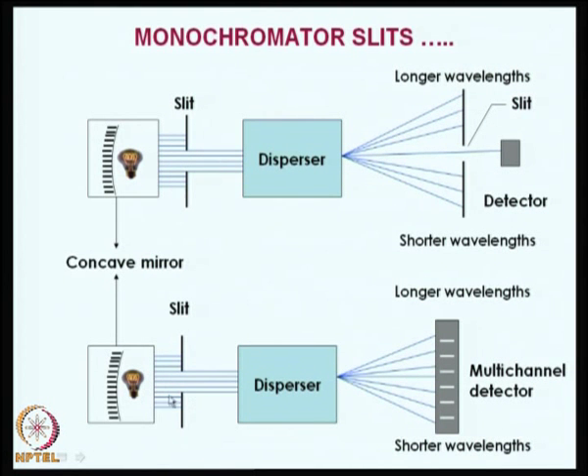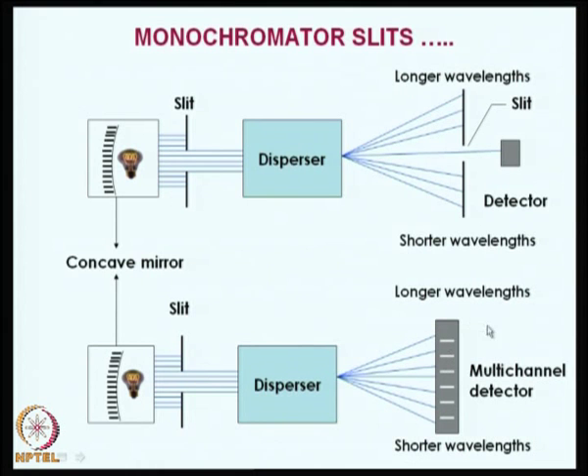We can place a detector at the end of the exit slit and collect the radiation coming through the second slit. In the bottom configuration, we can have a multichannel detector which can collect all the wavelengths coming out from the disperser. For example, if you have a prism, you will remember that seven colors come out of white light, and the same thing is true with diffraction units. If I place a multichannel detector at the end of the slit, I can collect all the information related to the incident radiation.